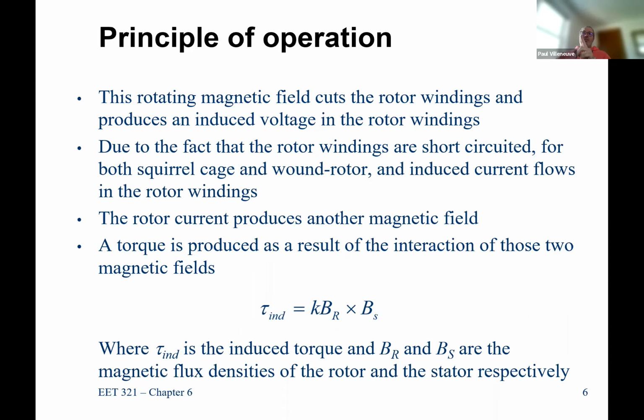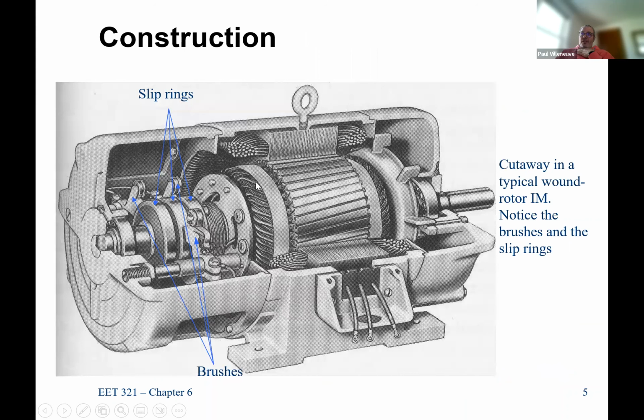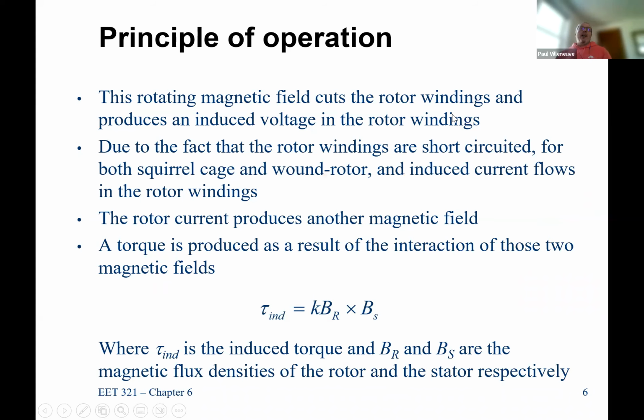Now, here's the difference between the synchronous machine and the rotor machine. So that AC current is creating that magnetic field, exactly the same for a synchronous machine. The difference over here is in our rotor, which is this part right here. We see a magnetic field because we have a current flow in here, and that current flow through this iron is going to produce a magnetic field seen by the windings here. Well, I have a set of windings that sees a changing magnetic field, which in turn is going to get an induced voltage on those windings. Because I have a closed path here and the magnetic field is changing, I'm going to induce a voltage across there. And because the windings are short-circuited, you get a current flow. So ultimately, you really get a current flow, which produces the voltage.